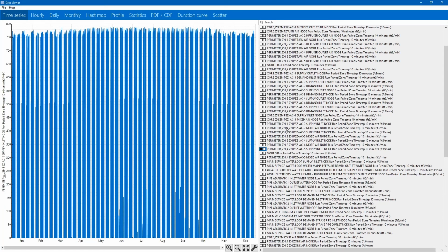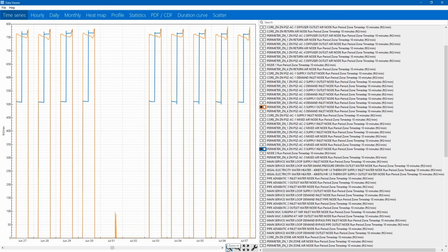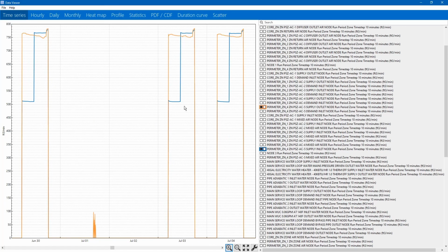Now we can do inlet node, outlet node. Okay, so first of all, you can see that in the middle of the day, the exhaust fan turns off and the return airflow jumps right back up. So you can see that during the first part of the day, the exhaust fan is on, and it's returning less air to the air handler.